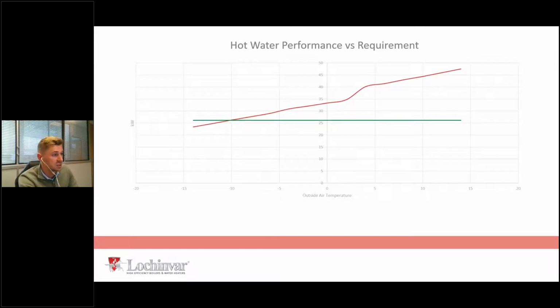So the performance curve we need, the green curve, is only 26 kilowatts, and that's because it just happens to be 26 kilowatts that we need to give a 1,000 litre storage volume a 2-hour heat up time. And we'll go into that just now as to why. So this heat pump, 45 kilowatt heat pump, is over spec. What I'd be doing in real life on this job is I'd be offering you a 30 kilowatt heat pump instead, because this one is going to basically give you a design temperature of -10. So unless you're in the Highlands of Scotland and watching this seminar, this is an over spec heat pump.